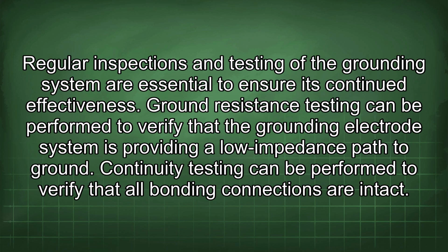Regular inspections and testing of the grounding system are essential to ensure its continued effectiveness. Ground resistance testing can be performed to verify that the grounding electrode system is providing a low impedance path to ground. Continuity testing can be performed to verify that all bonding connections are intact.